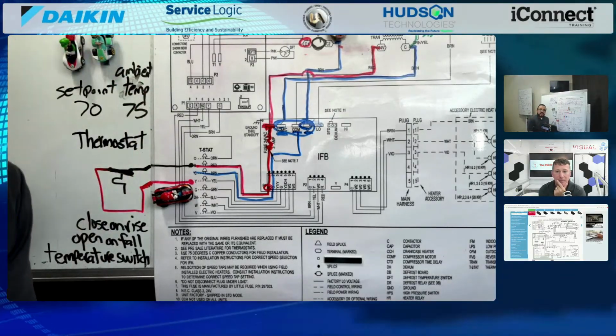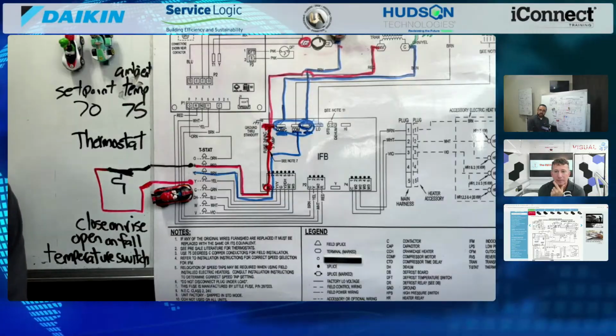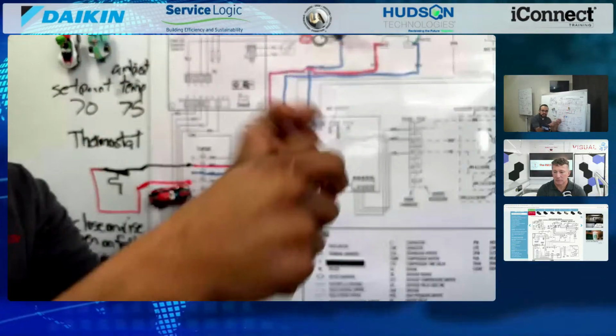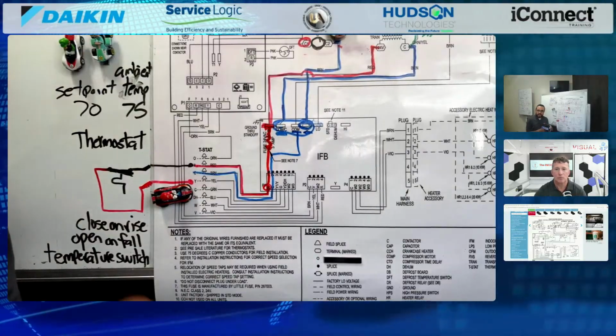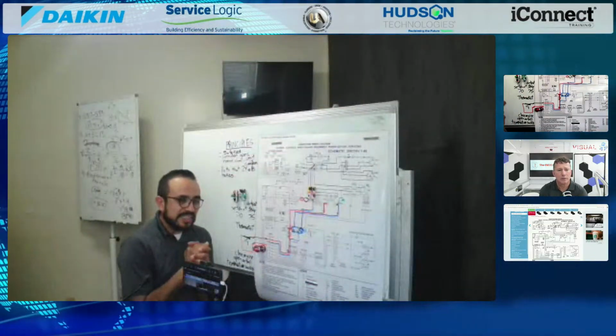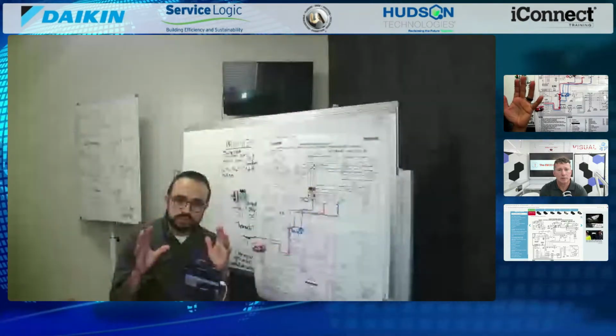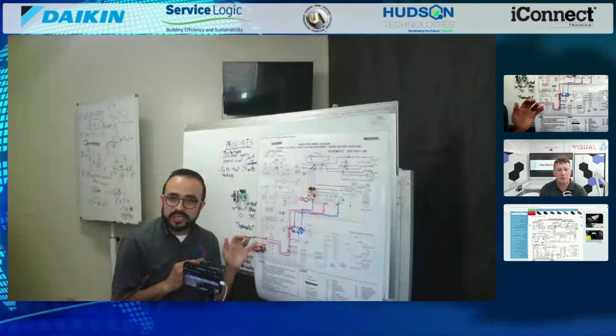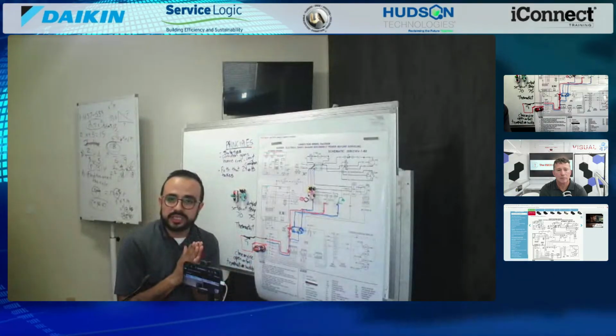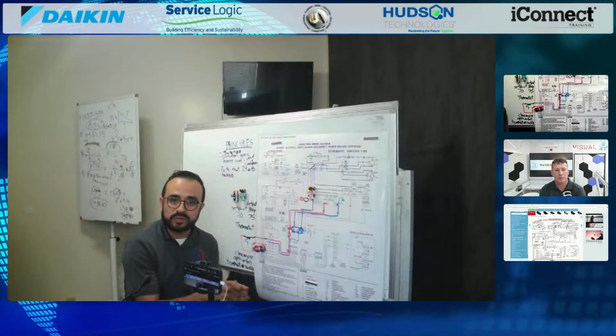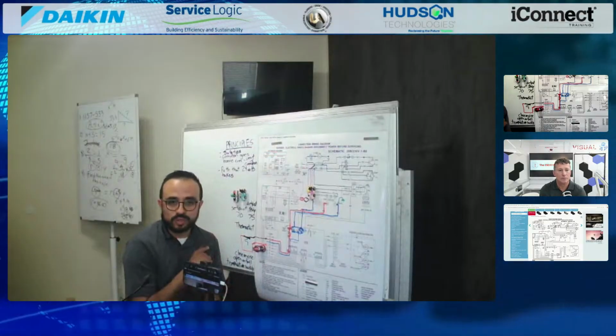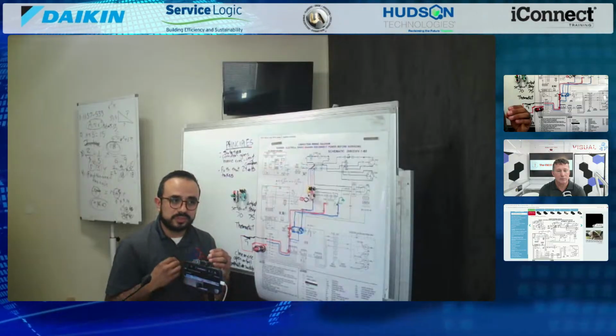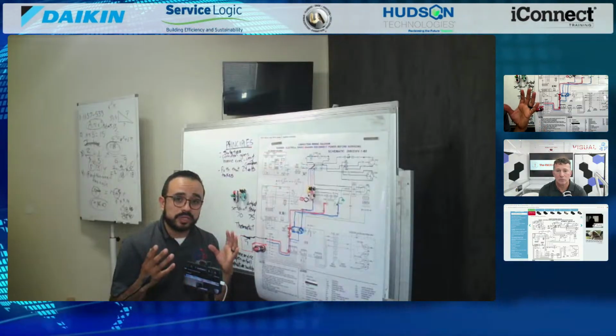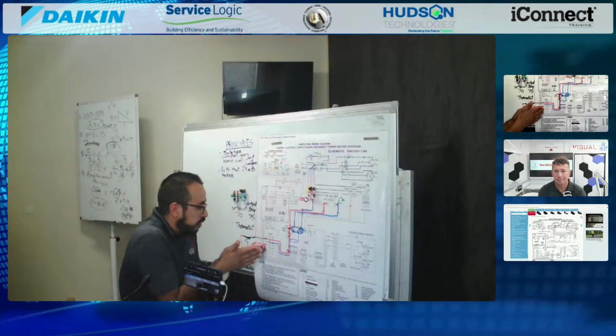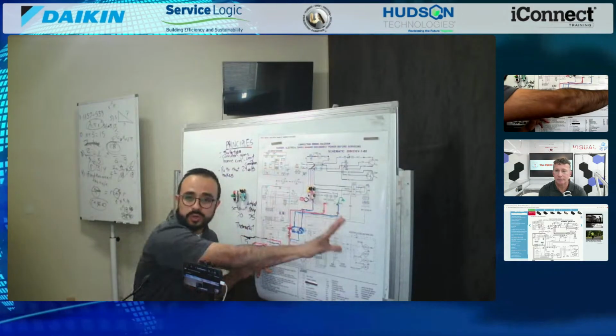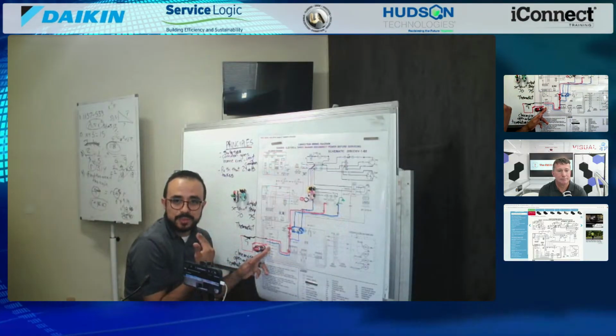I actually had a student today, he was trying to troubleshoot a system, and he was checking safeties, he was checking the board, he was going all out, and I'm like, okay, did you check if you have 24 volts between Y and C? Did you just check that one thing? I'm like, oh I haven't checked. Oh okay, let me check. I don't have 24 volts. Okay, so then let me check my thermostat. Because a lot of the times, a lot of people say it's a bad board. But what I always say is, if you're not getting 24 volts here on Y, don't work your way forward, work your way backwards. Something's happening.